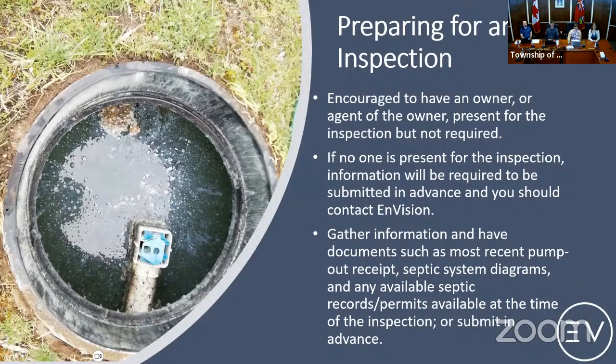And for this picture, we are looking at the outlet side of the tank. And we know that because we can see that little blue funny shaped thing in the pipe. So what we're actually looking at is the outlet pipe, and the vertical part where the blue thing is sticking in is called your baffle. It's to help ensure that solids are not going to exit through that outlet pipe. And that blue thing is an effluent filter.